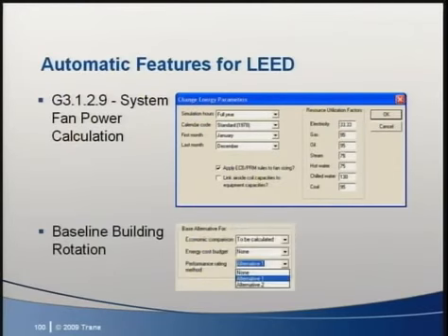The automatic system fan power calculation allows for automatic fan resizing. The fans will automatically be sized to follow the mentioned Appendix G requirements. In Calculate and View Results, if the user has chosen base alternative for the performance rating method, Trace will automatically determine the maximum fan energy when apply ECB PRM rules to fan sizing is checked in Change Energy Parameters. The baseline building performance shall be generated by simulating the building with its actual orientation and then rotating the entire building 90, 180, and 270 degrees, then averaging those results.